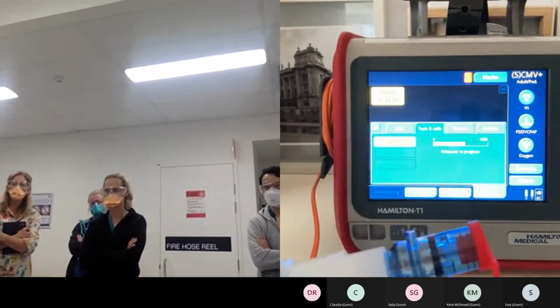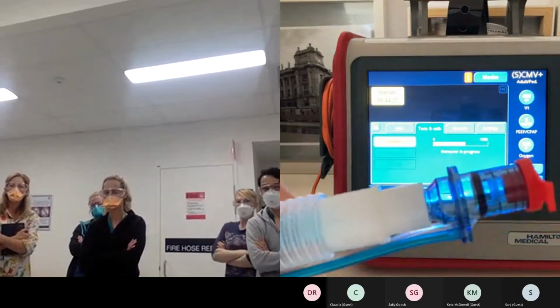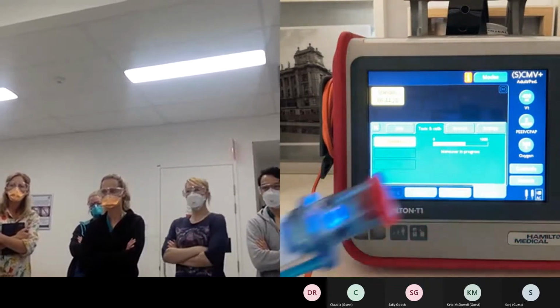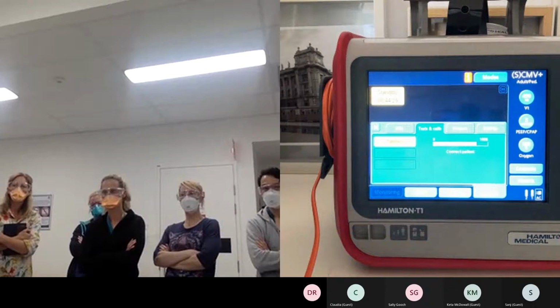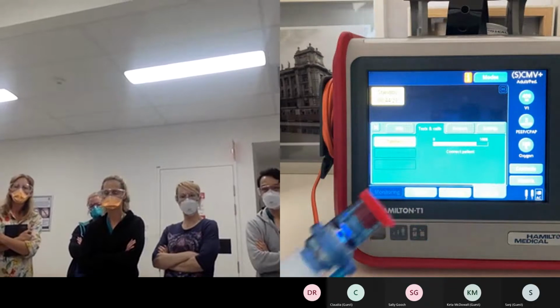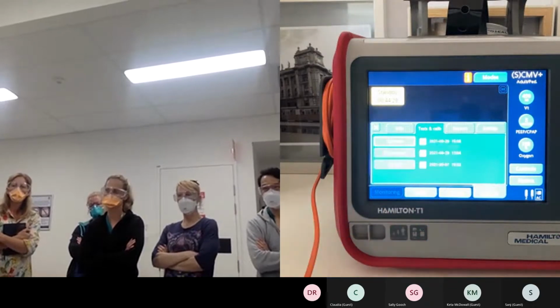Okay. If the cap has gone missing, it's not the end of the world. You can use a gloved hand to run this test as well. So you want to hear that sound, which is like it's releasing the pressure out the expiratory valve. So that's a good sound.